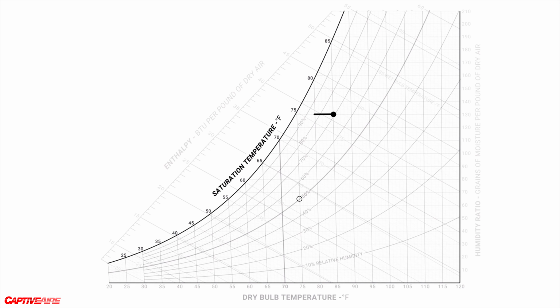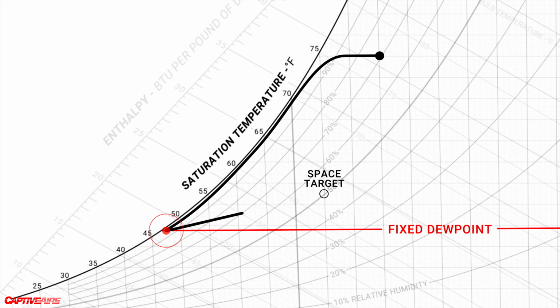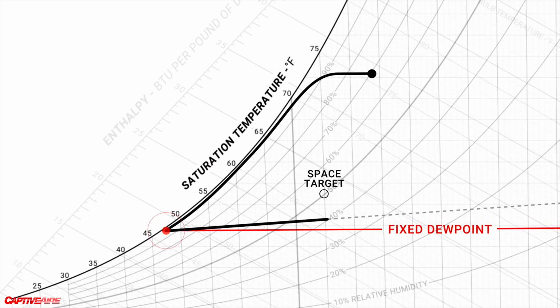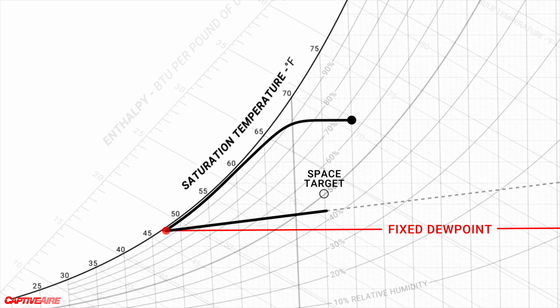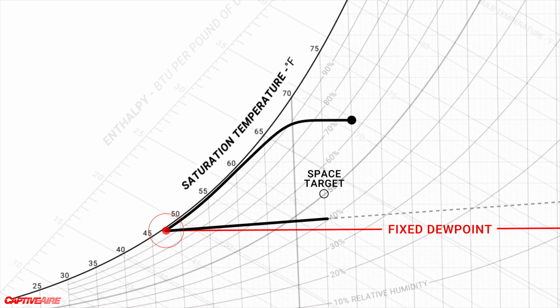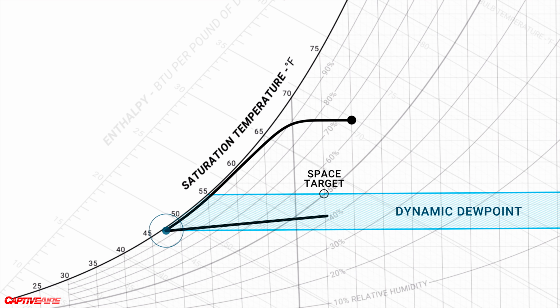Looking at the psychrometric chart, this cooling curve shows cooling to a fixed, worst case scenario dew point. This much latent cooling may be needed when the internal heat gains and sensible heat ratio require it. But in less than peak conditions or when the SA chart changes, it ends up causing an overly dry space. With dynamic dew point, we can adjust how much latent cooling takes place within a range, and the unit will actually monitor the space conditions and adjust the dew point accordingly.